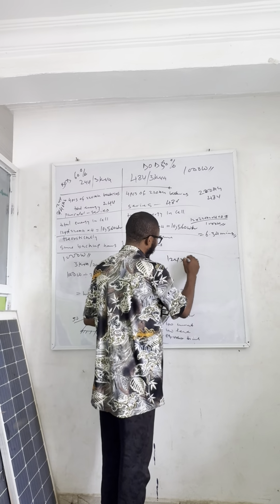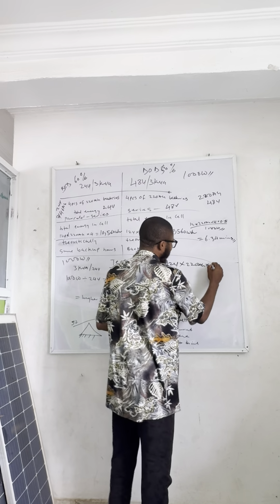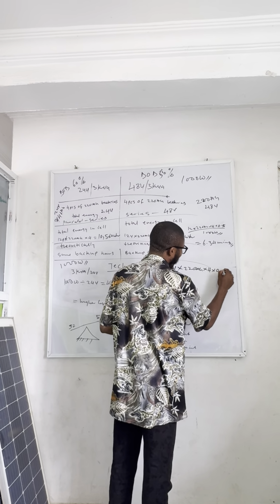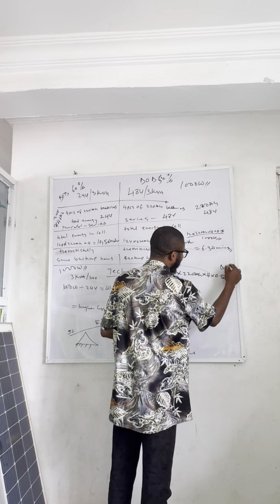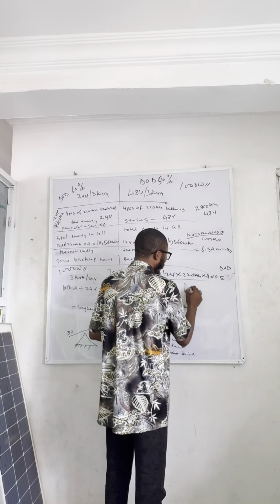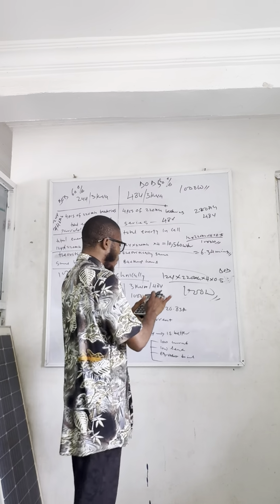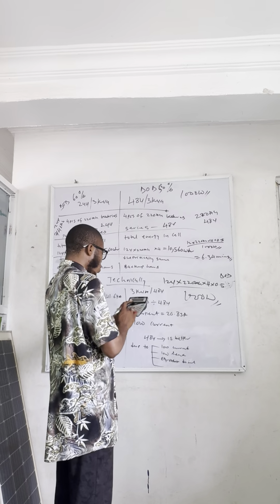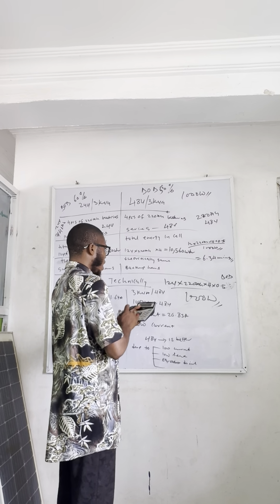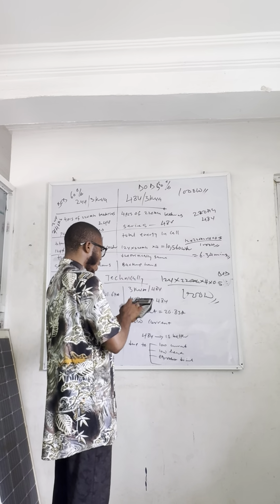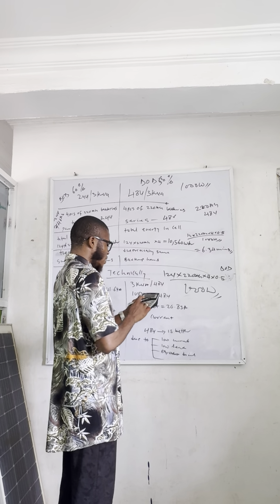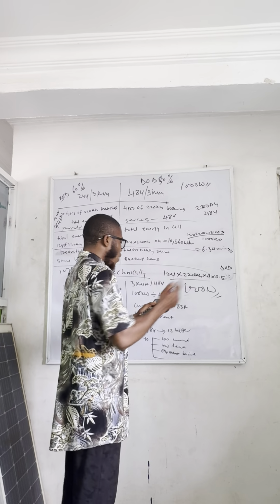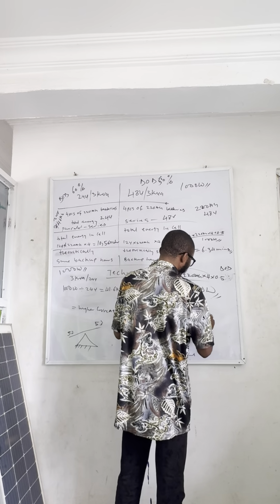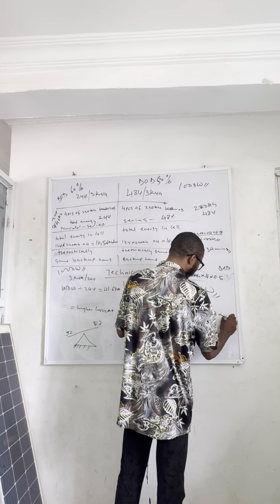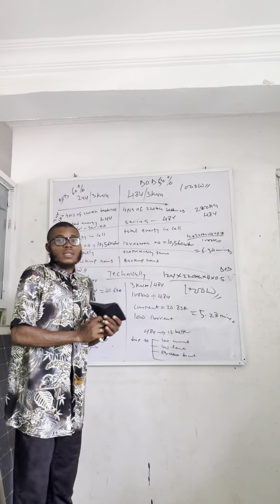What is going to be our likely backup power? That is equal to 12 volts multiplied by 220 amps multiplied by how many units? 4. Multiplied by the DOD, which is 0.5. What is the total load? That is 1000. Therefore, what is going to be our backup hours? That's 12 volts multiplied by 220 amps multiplied by 4 pieces multiplied by 0.5, which is 5,280, divided by 1000. So our expected backup time is 5 hours 28 minutes. Theoretically, they are going to back up for the same time.